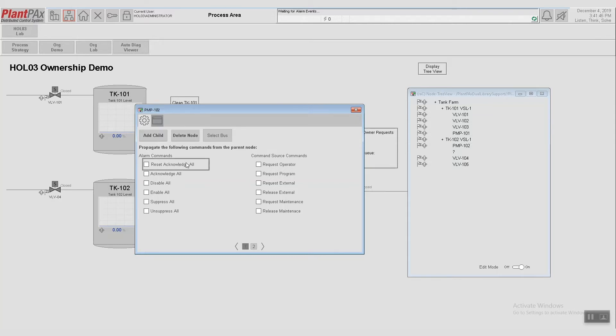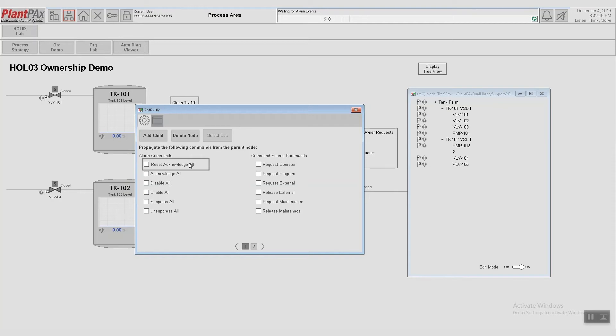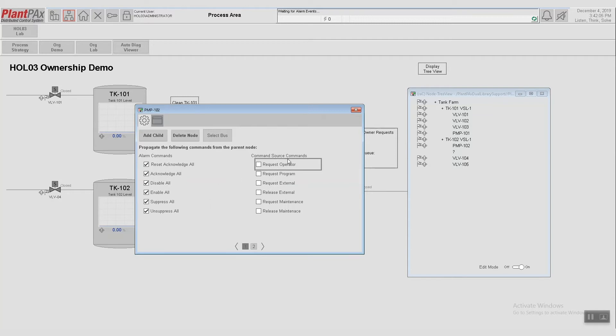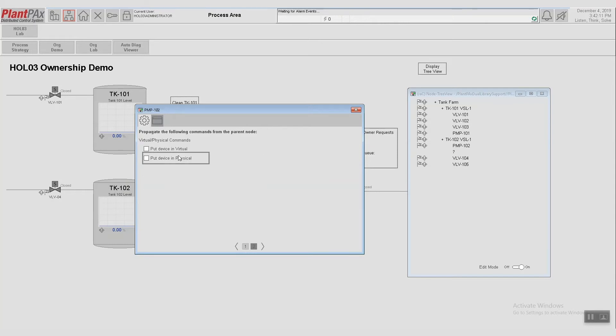The other thing we see on this screen is propagate the following commands from the parent node. So here we can set what we want pump 102 to accept from Tank 102 or from Tank Farm, anything that has that device in its organizational tree. So we have options for alarming, which we'll go ahead and select. We have options for command source. And lastly, we have options for if we wanted to be able to put a device into virtual or physical mode.